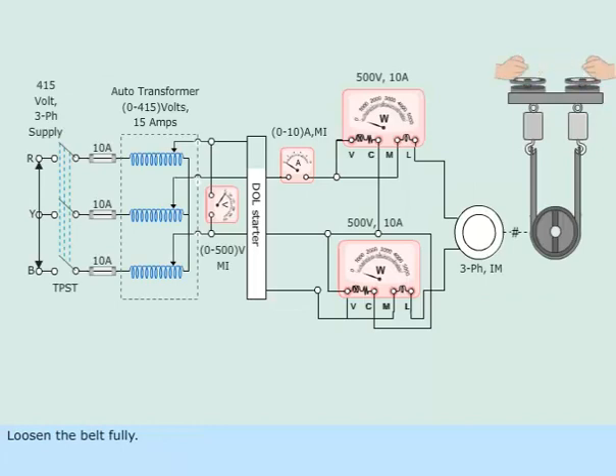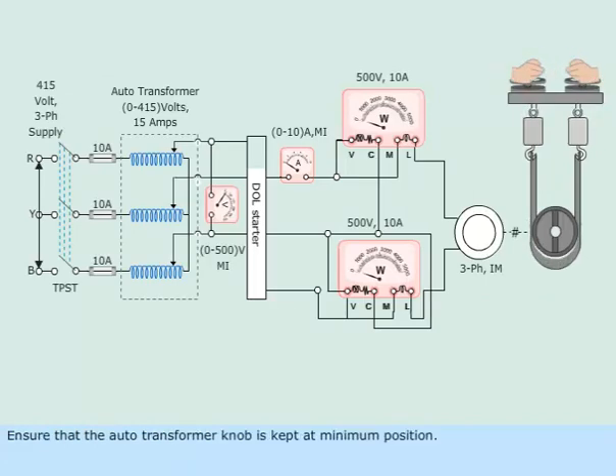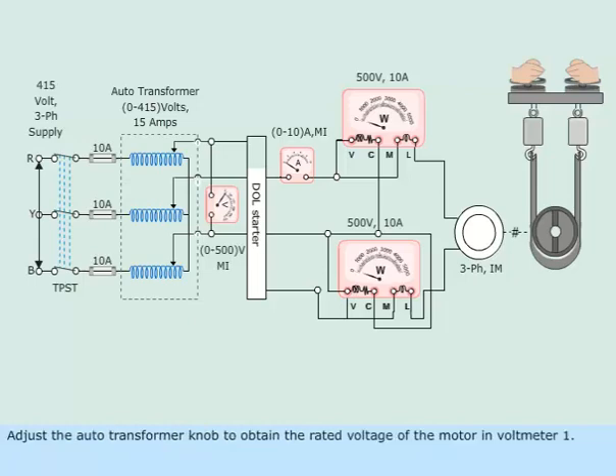Loosen the belt fully. Ensure that the auto transformer knob is kept at minimum position. Switch on the power supply to the motor. Adjust the auto transformer knob to obtain the rated voltage of the motor in voltmeter 1.